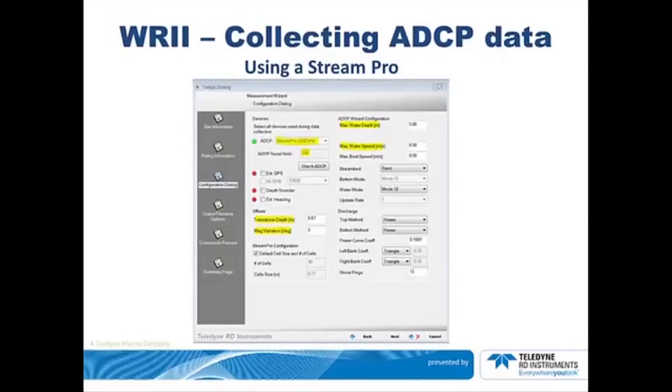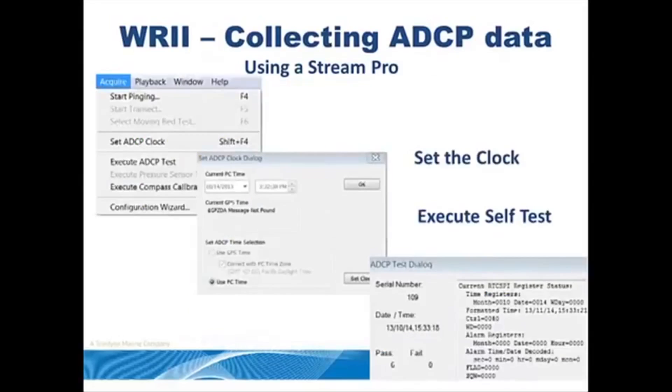Proceed through the remainder of the wizard by clicking Next. Click the Acquire drop-down menu and select Set ADCP Clock. The StreamPro clock will then be set based on the laptop time, date, and time. Click Execute Self-Test and observe that there are 6 passes and no failures. For this test, the transducer should be in non-moving water. If you have a failure, you can investigate it yourself or contact us.